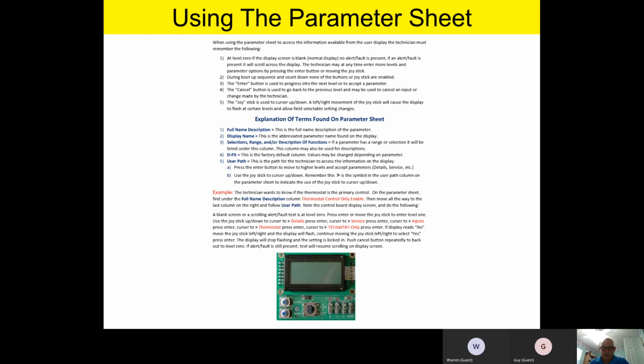Now, once I do that, if the display reads no, then I'm going to move my joystick left and right to get it to flash. Remember, when you get a flashy screen, that means you can change it. So you get a flashy screen, and then you move your joystick left and right to select yes in this example, and then press enter. Now at that point, what you've just told the board is that you're driving it by a thermostat only. And so that's just one example of many parameters that you can find on the parameter sheet.